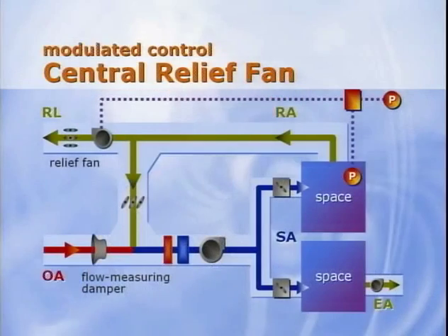Since the relief fan is located outside of the ventilation loop, the energy benefits to the system are greatest when the fan is off. In many buildings, this could be any time the system isn't economizing. The disadvantage of the relief fan being outside of the ventilation loop is that the return duct static must be added to the supply fan. This will require a higher horsepower selection. Of course, building pressure can be controlled using either fan configuration.